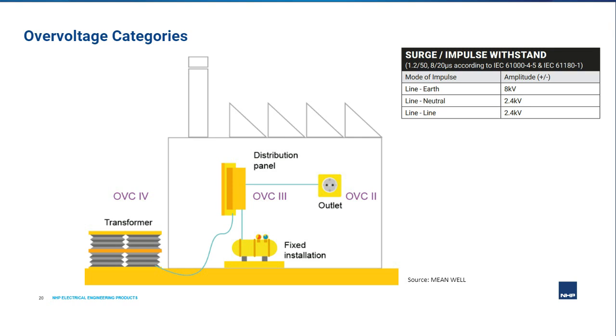For most applications using liveline indicators, we see it being installed and used at this level, and therefore it's again important to highlight that the upgraded REMLIVE unit, that's the RL24IC, has a monitoring voltage range from 24 to 1000 volts at Cat 3. Cat 2 category is for equipment that's supplied from a fixed installation, for example from the wall outlet that you can see in the diagram.